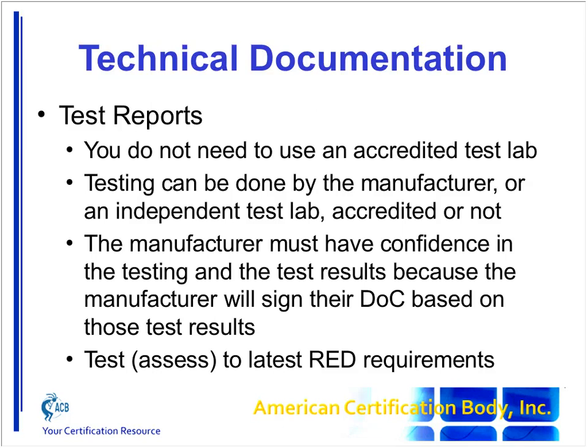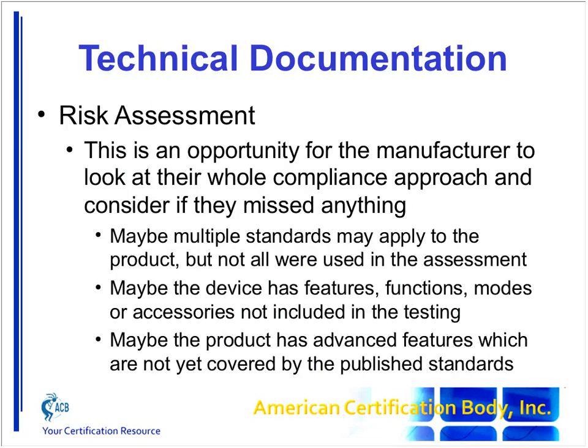So this risk assessment document, it's not like a standard safety risk assessment - that probably will have been dealt with by the safety testing. This is more of an opportunity for the manufacturer to step back at the final stage and look at their whole compliance approach and consider if they missed anything. Maybe they've applied a safety standard, but if they stop and think about it, there could be more than one safety standard that applies. Or same with EMC.